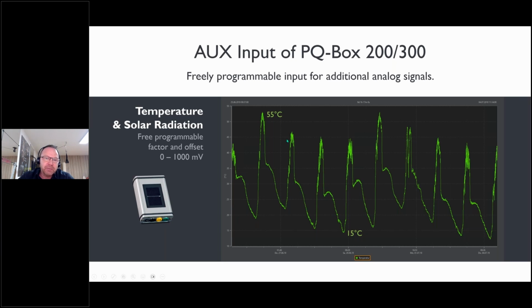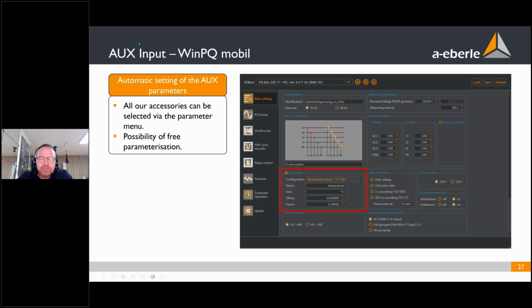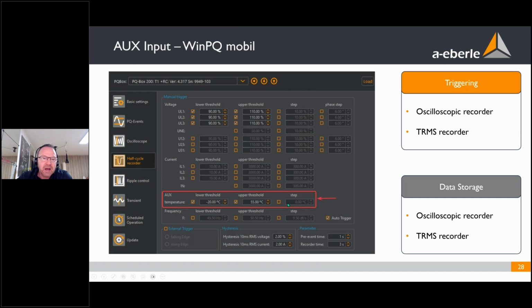Here's one example of a temperature measurement in a small cabinet outside in the field where our analyzer is installed. I was interested in how hot it gets during the summertime in Germany inside this cabinet, and we reached 55 degrees. Okay, that's normal, and our analyzers, as I said, are produced for outside temperatures up to 60 degrees. If you're using the aux input, you activate it in our software, and here you have a wide field of different sensors. If I tell the box I'm connecting a temperature sensor from -20 to 80 degrees, then in our software at oscilloscope and trigger, the aux input is also active, and we can even trigger on a temperature or differential current or PE current. So many applications are possible here.